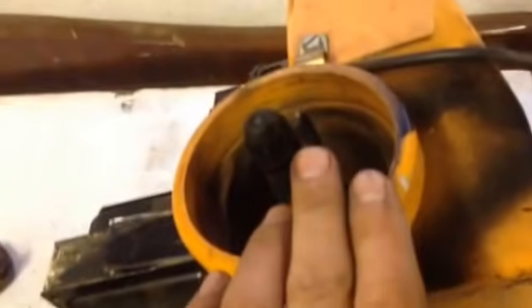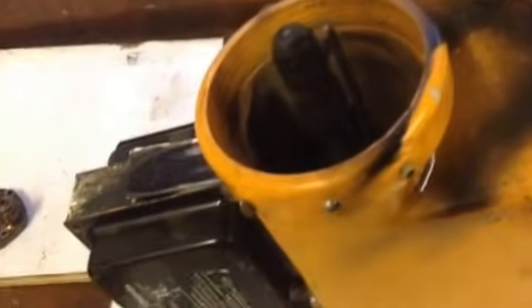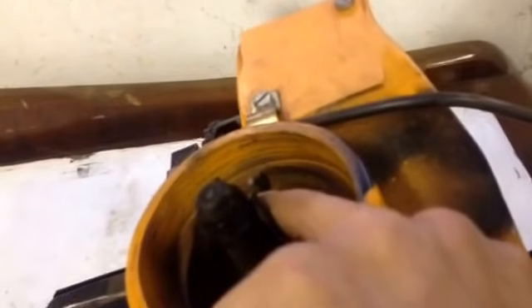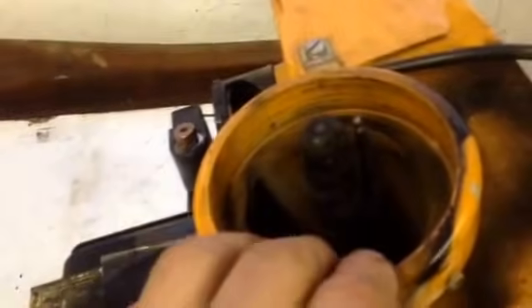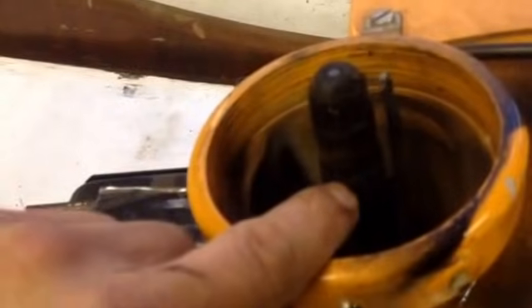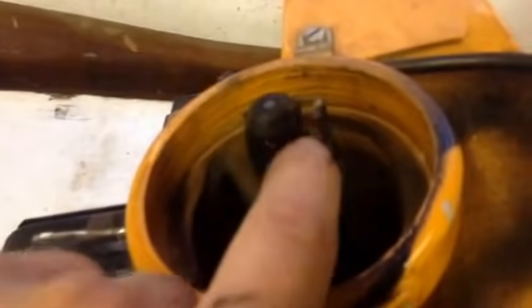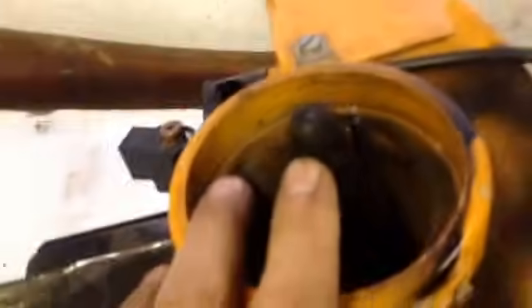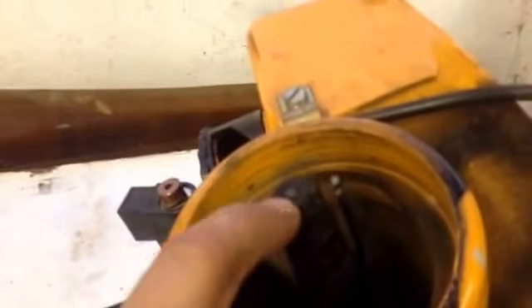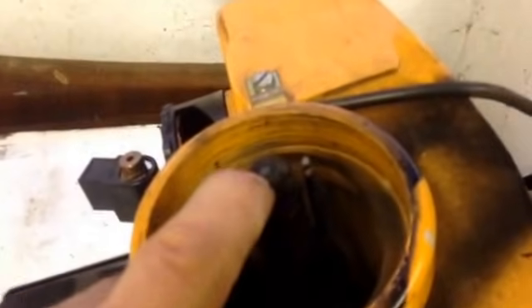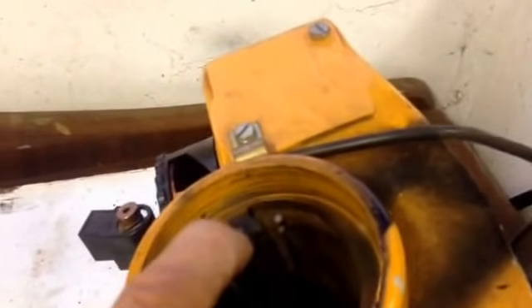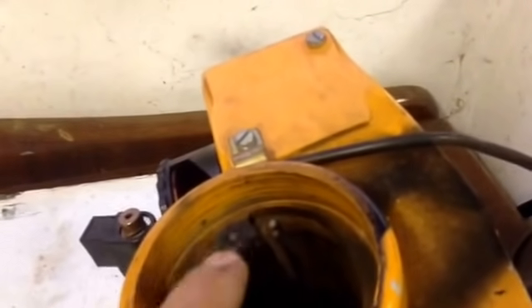Okay, so you want to look to make sure there's a reasonable spark gap. Have a look in the manual, but you can probably say somewhere in the region of 3-4 mil or a bit more. If it's burning badly, another thing is these nozzles just undo, so you can take the nozzle out, read the side of it, and get a new one from eBay. There are marks on the side to say what it is - you can Google it and get a new one. You can tell when one of these has gone usually because either there's muck in the boiler where it's burning black, or sometimes you find they're wet at the end, which means it's not atomizing properly. If it's wet at the end, it should be dry.